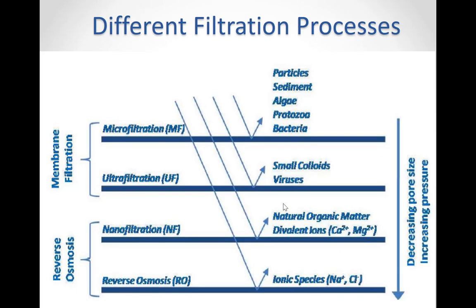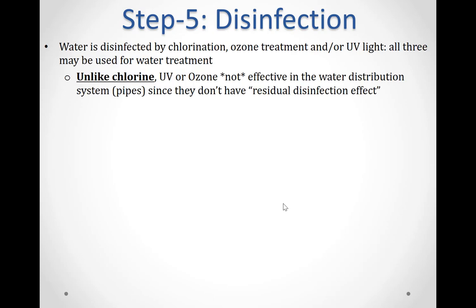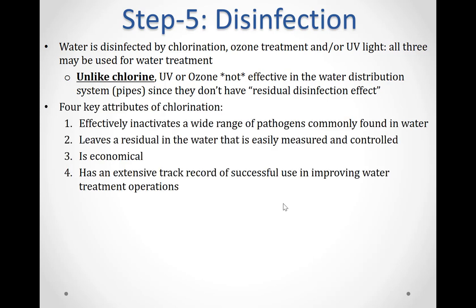In the diagram that follows, you can see different membrane filtration processes and what they can be used for. The fifth step is disinfection. After water has been filtered, a disinfectant may be added in order to kill any remaining parasites, bacteria, and viruses, and to protect the water from germs when it is piped to homes and businesses. Chlorine, ozone, and UV light may all be used as disinfectants. Unlike chlorine, however, UV or ozone are not effective in the water distribution system since they don't have a residual disinfection effect. Chlorine has four key attributes: one, it effectively inactivates a wide range of pathogens commonly found in water; two, it leaves a residual in the water that is easily measured and controlled; three, it is economical; and four, it has an extensive track record of successful use in water treatment operations.